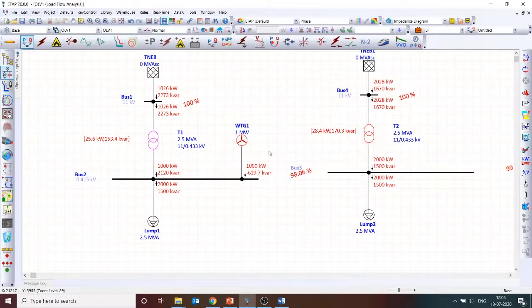But the beauty is, 2000 kilowatt is my demand. 1000 kilowatt is generated by my wind turbine generator. So I need to draw only 1000 kilowatt from the utility. With a loss of 25.6, I am drawing 1026 kilowatt from here. That means I will be billed only for 1026 kilowatt. That means approximately, I will consume only 1000 units and my bill will reduce from 16,000 to 8,000. Correct? I have reduced the consumption by half. So my electricity bill with respect to the energy consumption will come down by half.